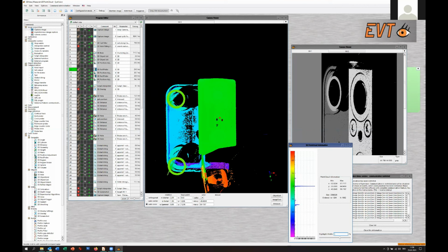position adjustment. The position adjustment rotates the image to the right position, and with the area adjustment, you do the flat, so that it's on the same level. That's why here, of course, you see this is nearly exactly the same level. So you can increase the width, and then you see it's only 1%. This is a nearly flat scan after the correction.